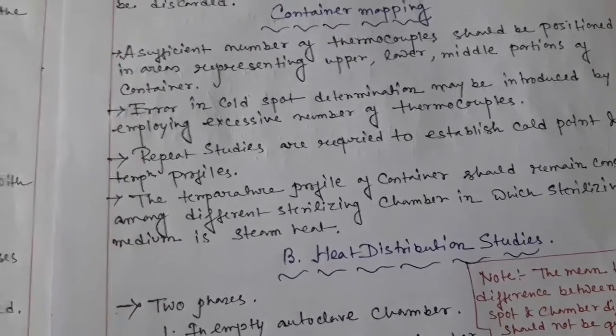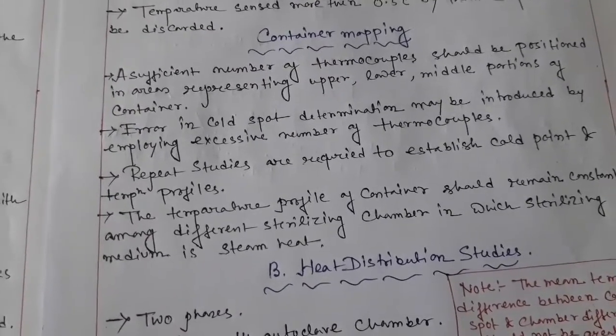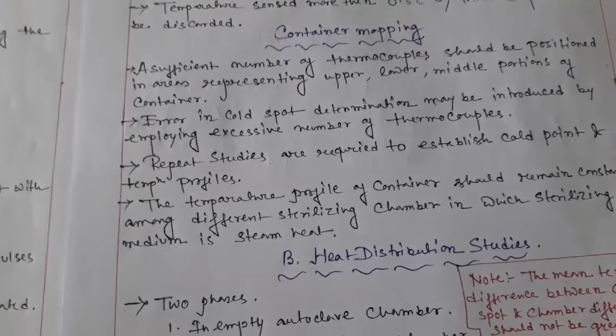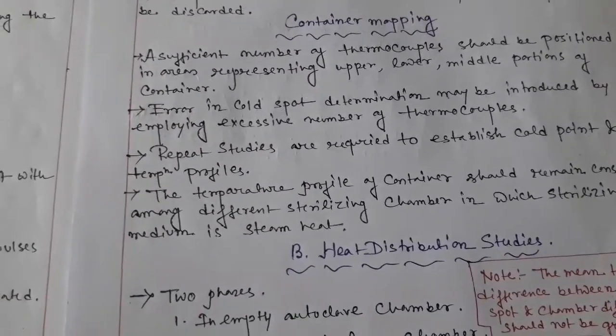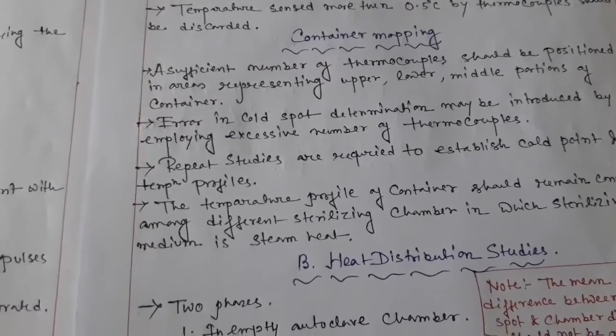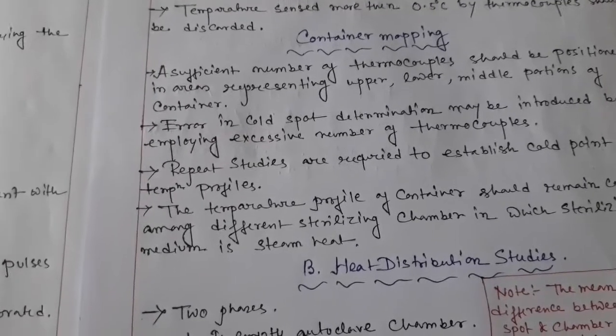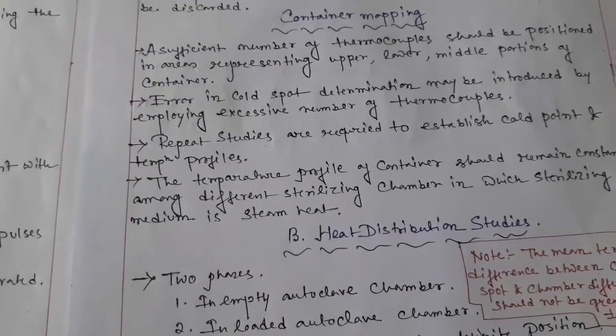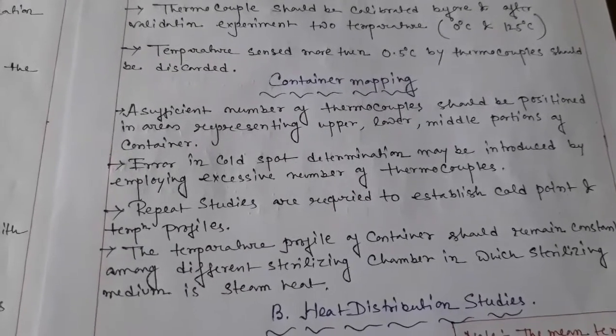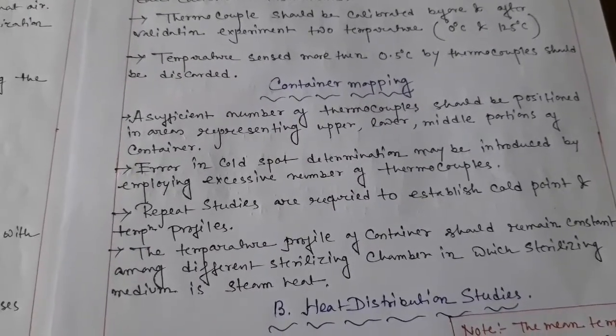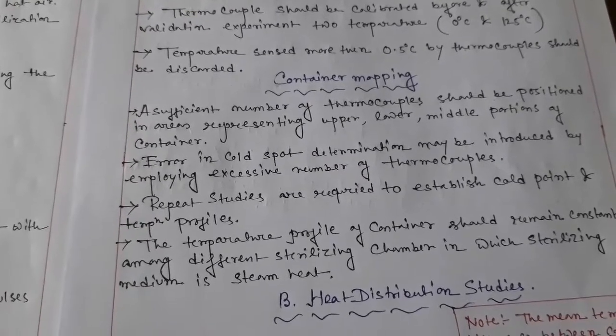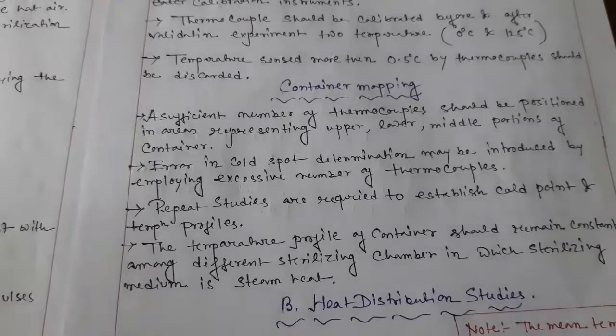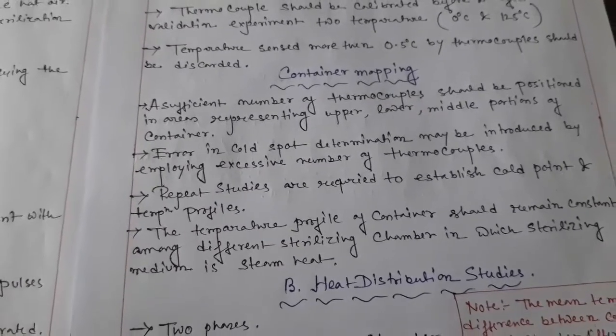Repeat studies are required to establish the cold point and temperature profiles. You have to repeatedly follow the studies when calculating the cold point and temperature. This is very necessary for container mapping validation. The temperature profile of the container should remain constant among different sterilizing chambers in which the sterilizing medium is steam heat.